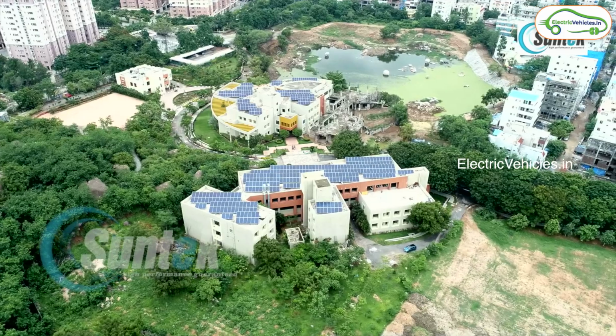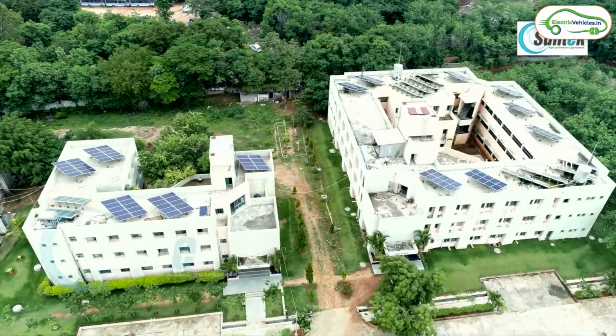In mono PERC we get up to 550 watt. So in the specified area, we can install up to 540 in mono PERC, and in poly up to 365 to 370 maximum. So how many units can 1 kilowatt solar generate in one day? Each kilowatt, on an average over 365 days, will generate around 4 units per day.